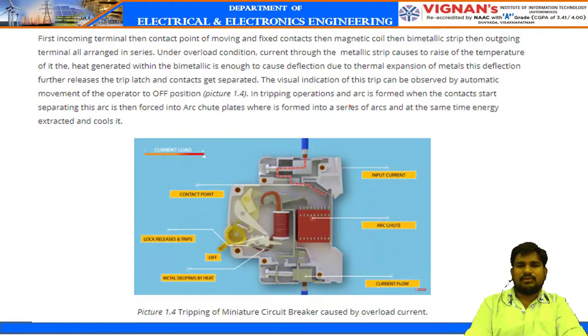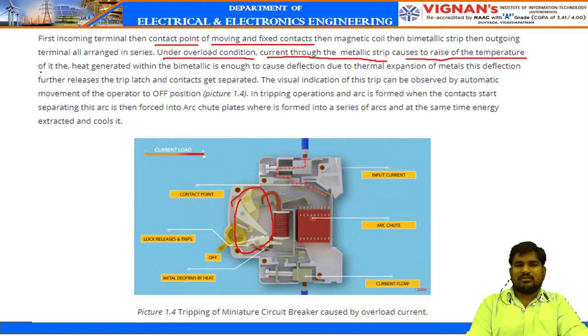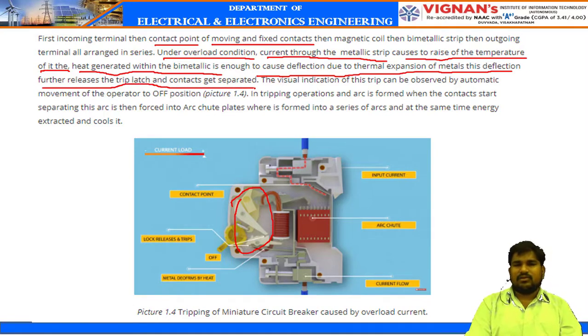Here we have two contacts, a fixed contact and a moving contact. Now let us come to case 1, that is overloading condition. Under overloading condition, the current through the bimetallic strip causes its temperature to rise. The heat generated within the bimetallic strip is enough to cause deflection due to thermal expansion of metals. This deflection further releases the trip latch and the contacts get separated. I am repeating, in case of overloading, the current through the strip raises its temperature, causing deflection by thermal expansion. That means the bimetallic strip has expanded and the metal contacts will get separated. So this is the first case, that is overloading condition.